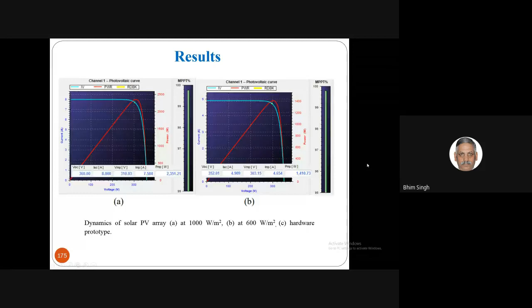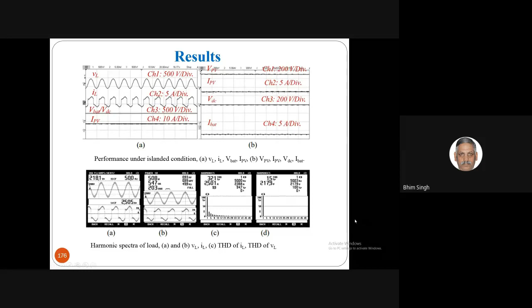The voltage is sinusoidal when the current is highly non-linear. You can see typically the THD of the voltage is 1.5% when it is feeding a load current with THD of 32%. So it is working as a very good UPS even with highly non-linear load, but the voltage is very close, only 1.5% THD. When the grid was not there, the inverter was feeding the load, I mean, the battery and inverter were feeding the load.